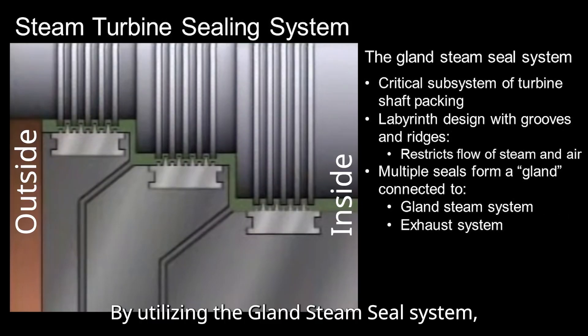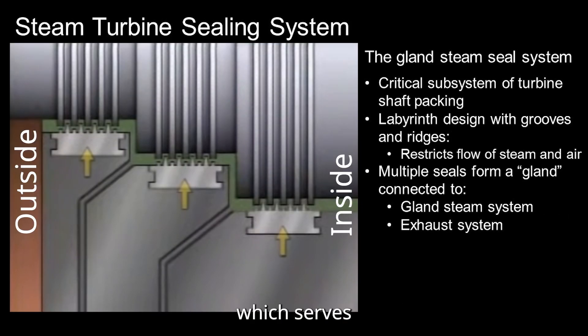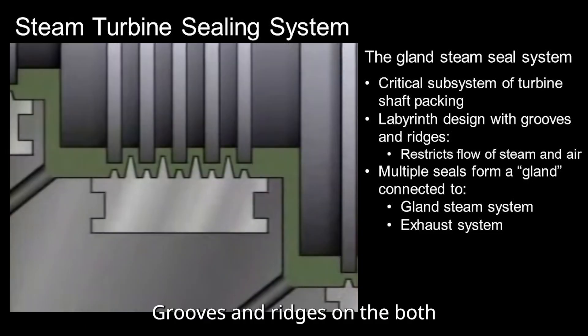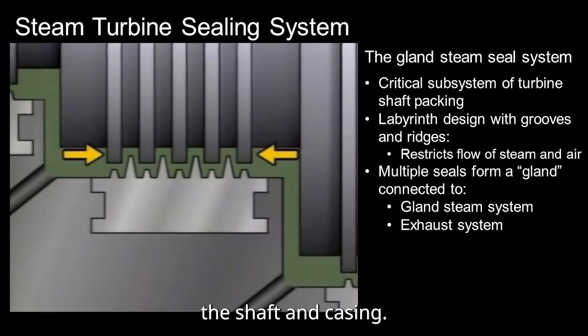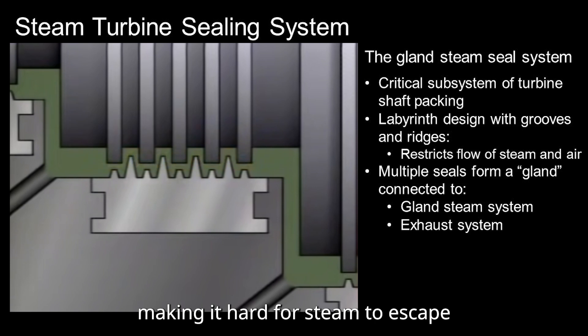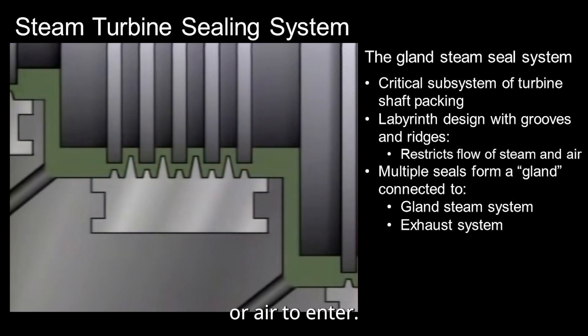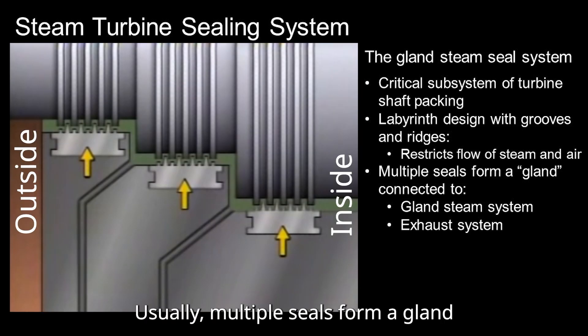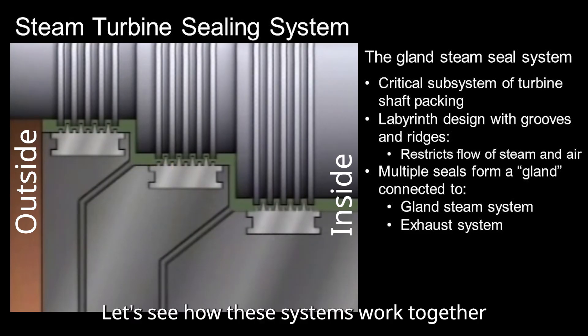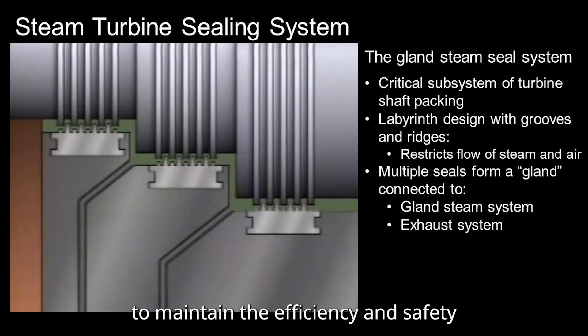So how do we stop this? By utilizing the gland steam seal system, which serves as a critical subsystem of the turbine shaft packing. These seals create a tortuous path using a labyrinth design — grooves and ridges on both the shaft and casing. This design restricts flow, making it hard for steam to escape or air to enter. Usually, multi-seals form a gland, which is connected to a gland steam system and an exhaust system.